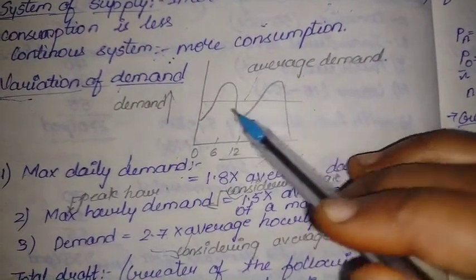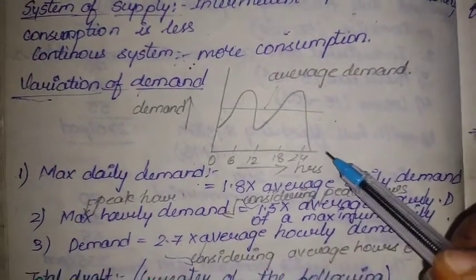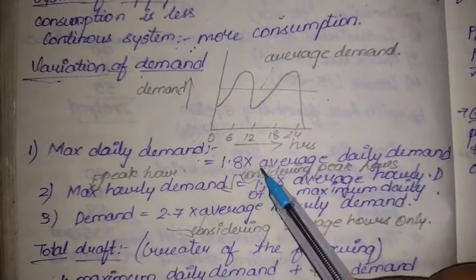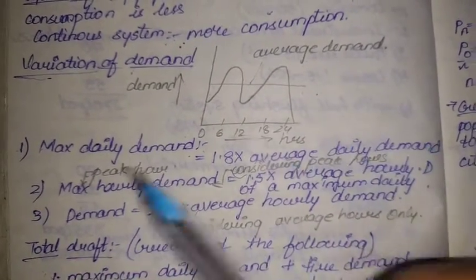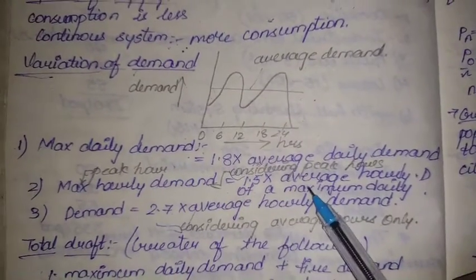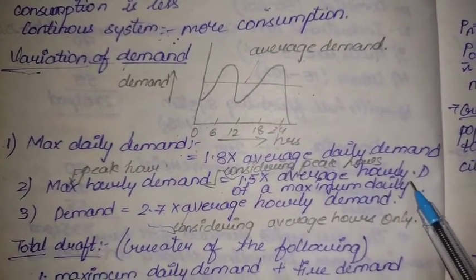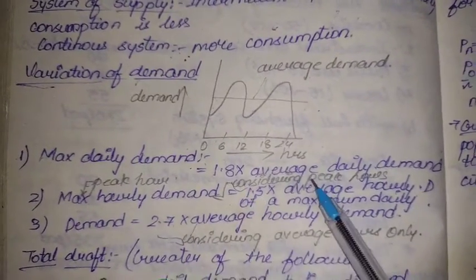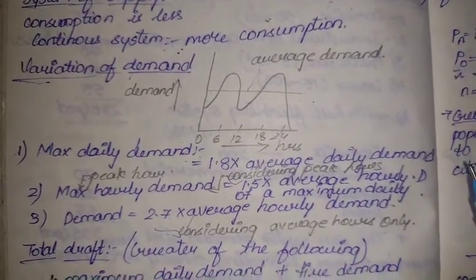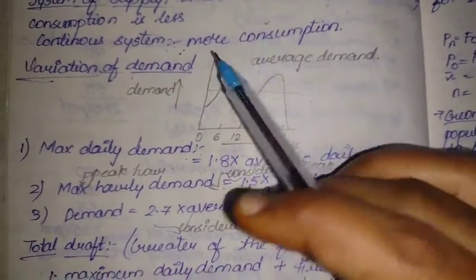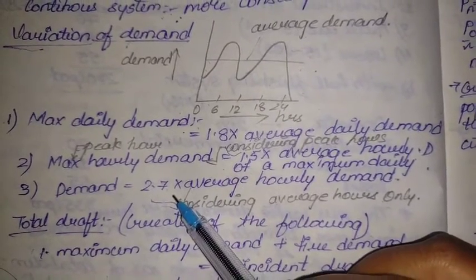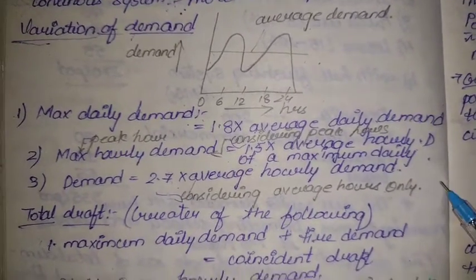The maximum daily demand is 1.8 times the average daily demand. The maximum hourly demand is 1.5 times the average hourly demand of the maximum daily. So the maximum hourly demand equals 1.5 × 1.8 = 2.7 times the average daily demand.